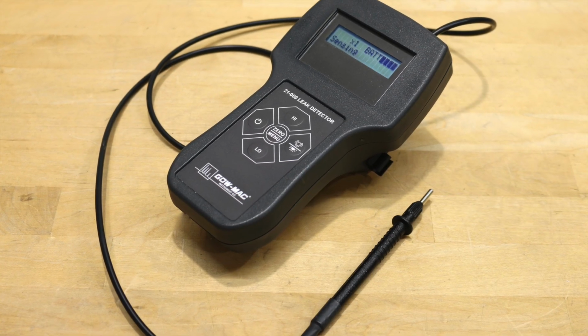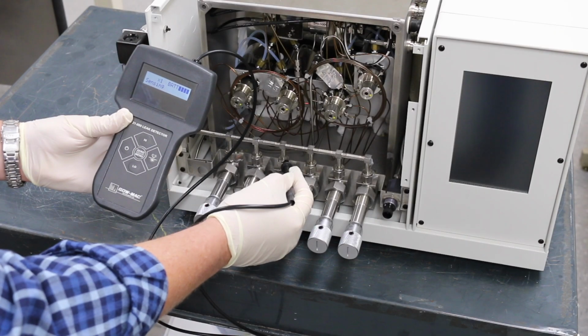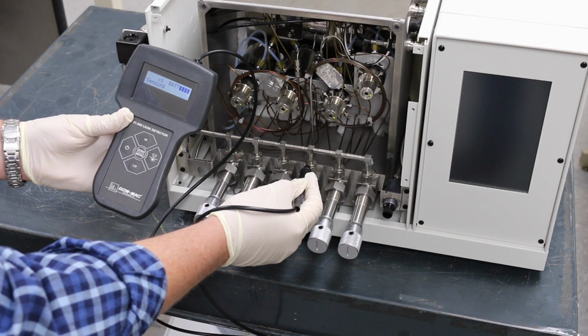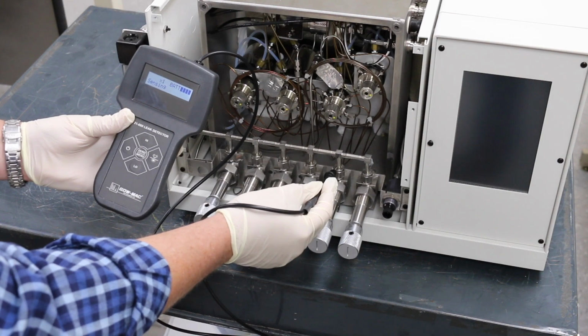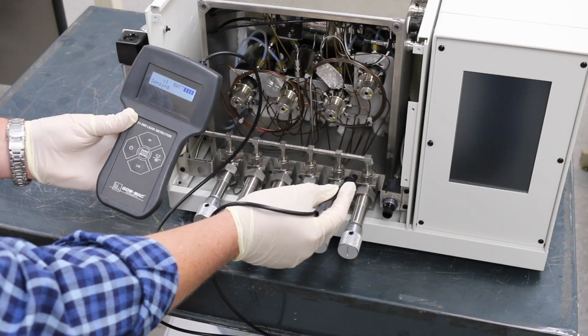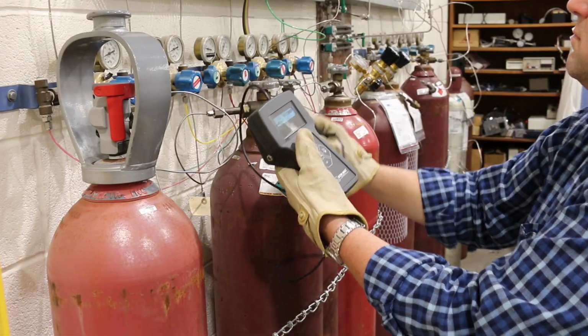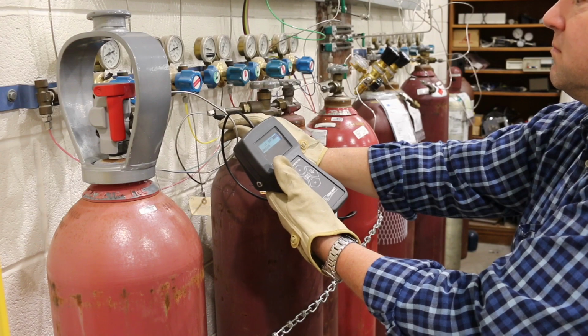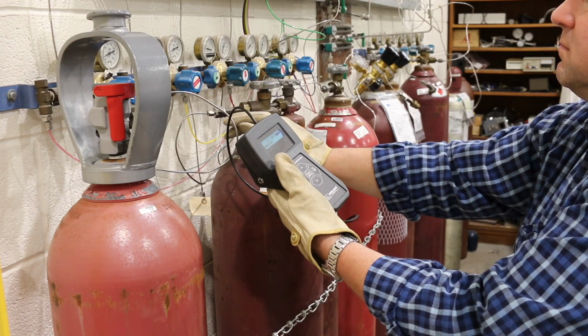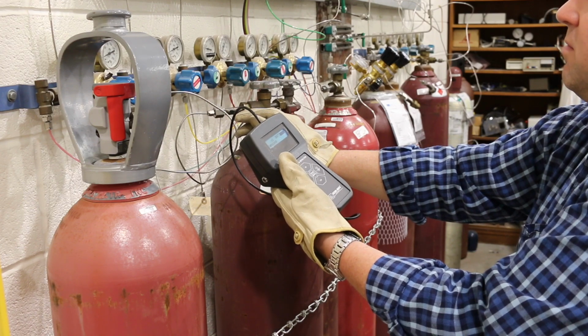GOW-MAC 21080 Mini Leak Detector. Accurate analyses require leak-free gas delivery systems. The GOW-MAC 21080 Leak Detector can help find even the smallest leaks. This handheld leak detector features a thermal conductivity cell with an adjustable sensitivity for low and high ranges. With a response time of just 3 seconds, leak detection has never been easier.